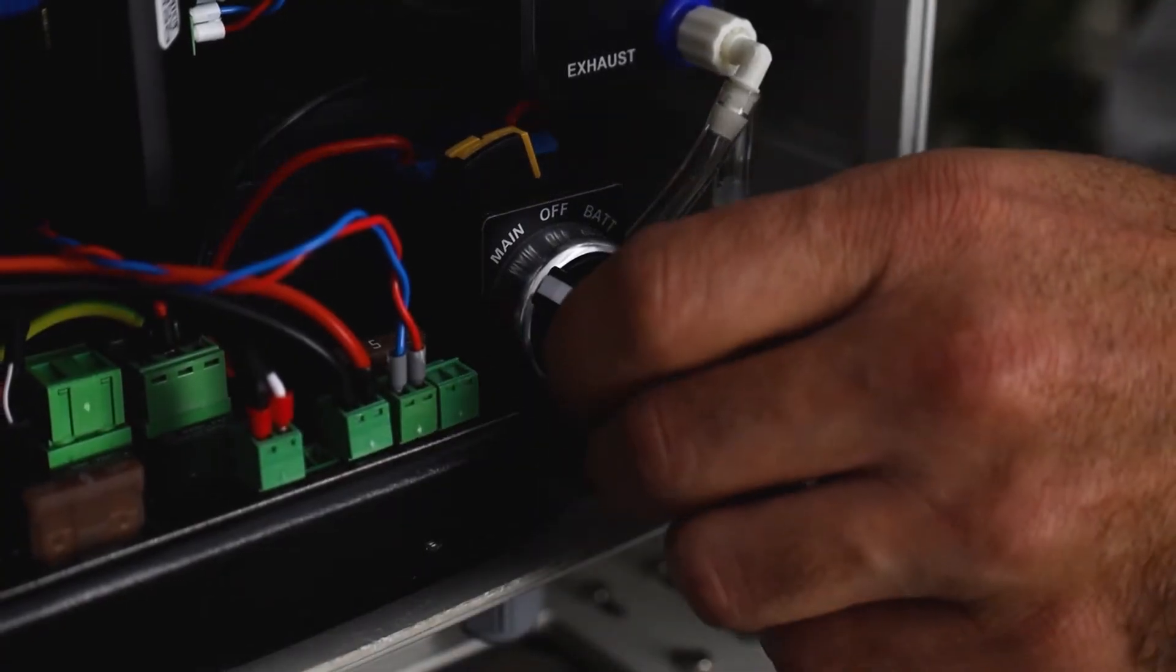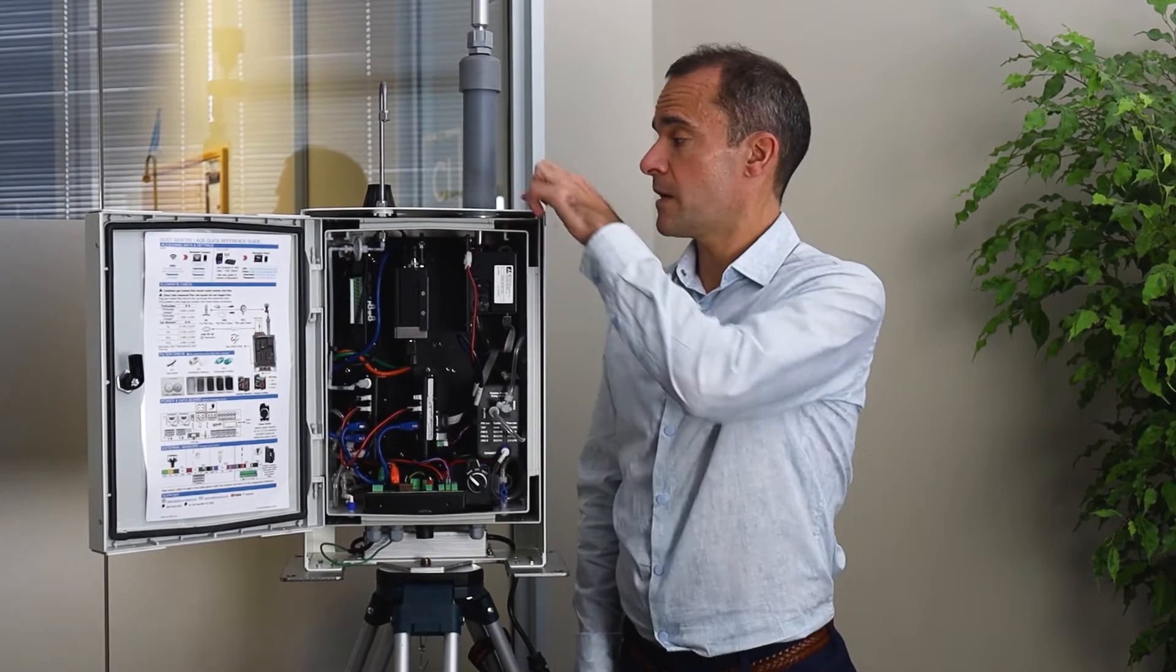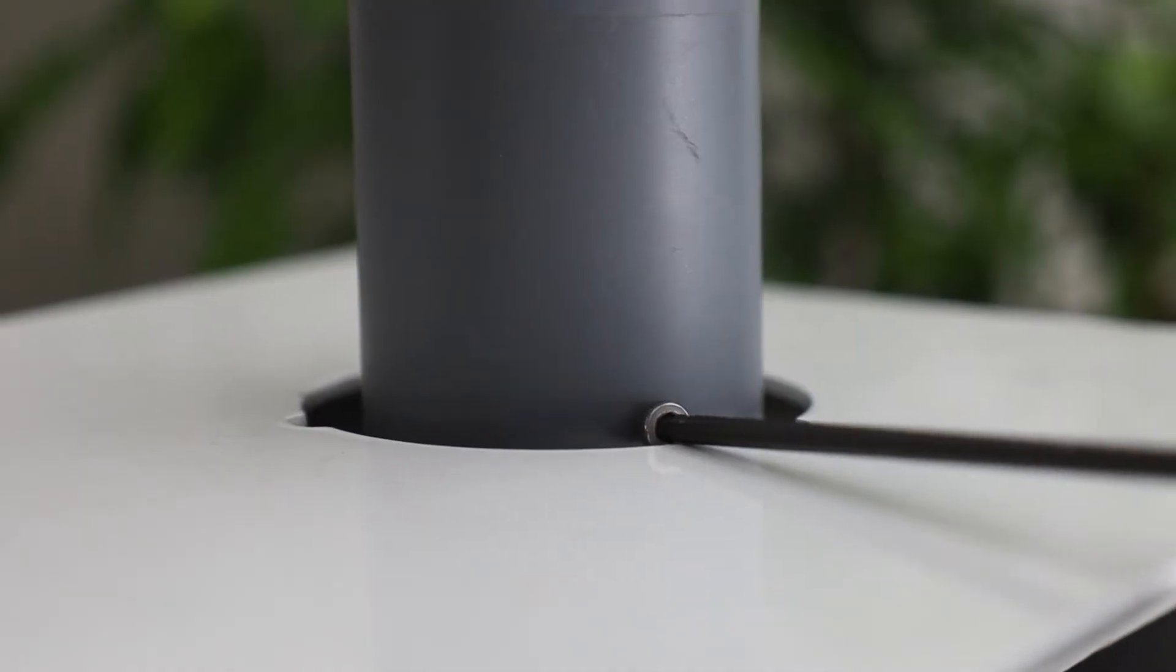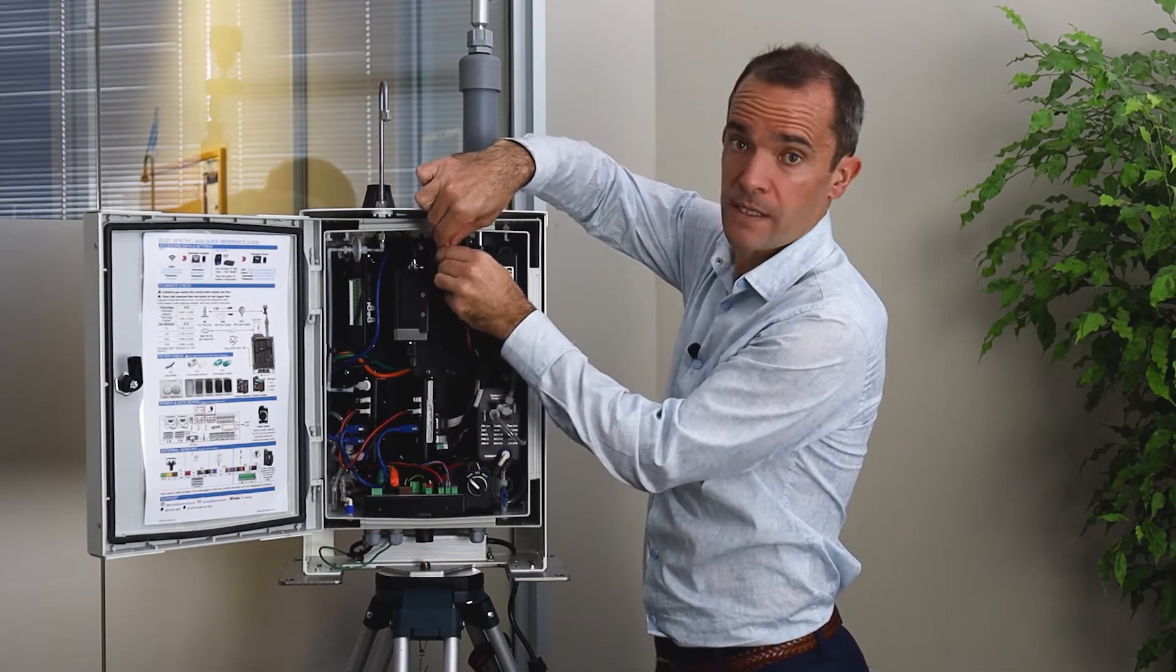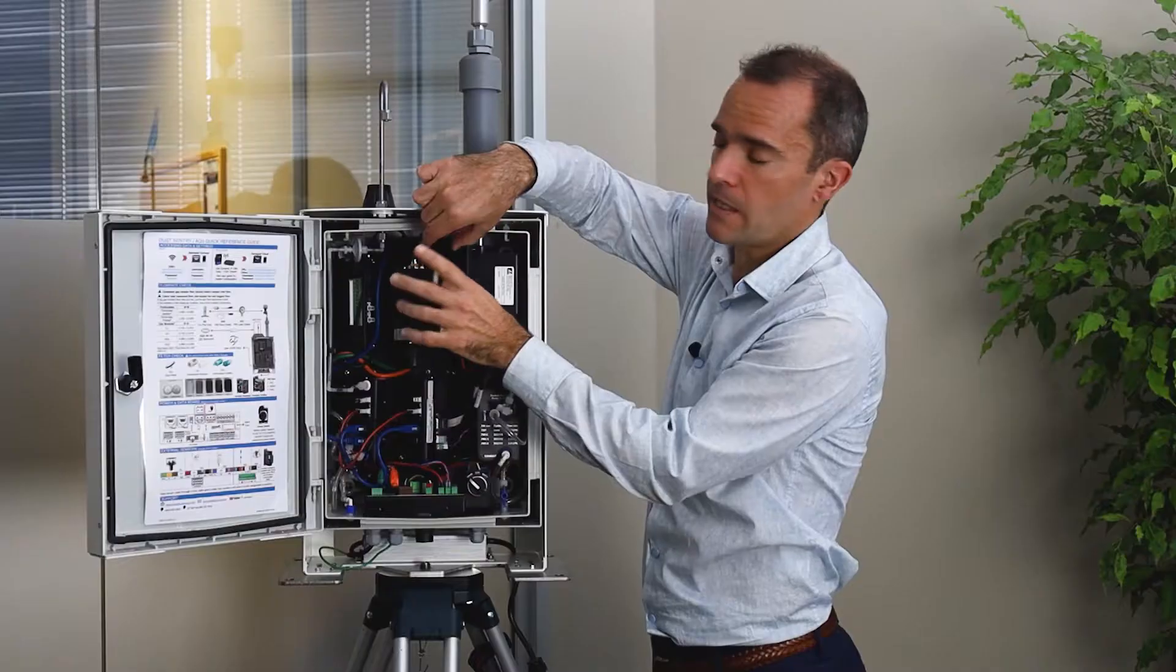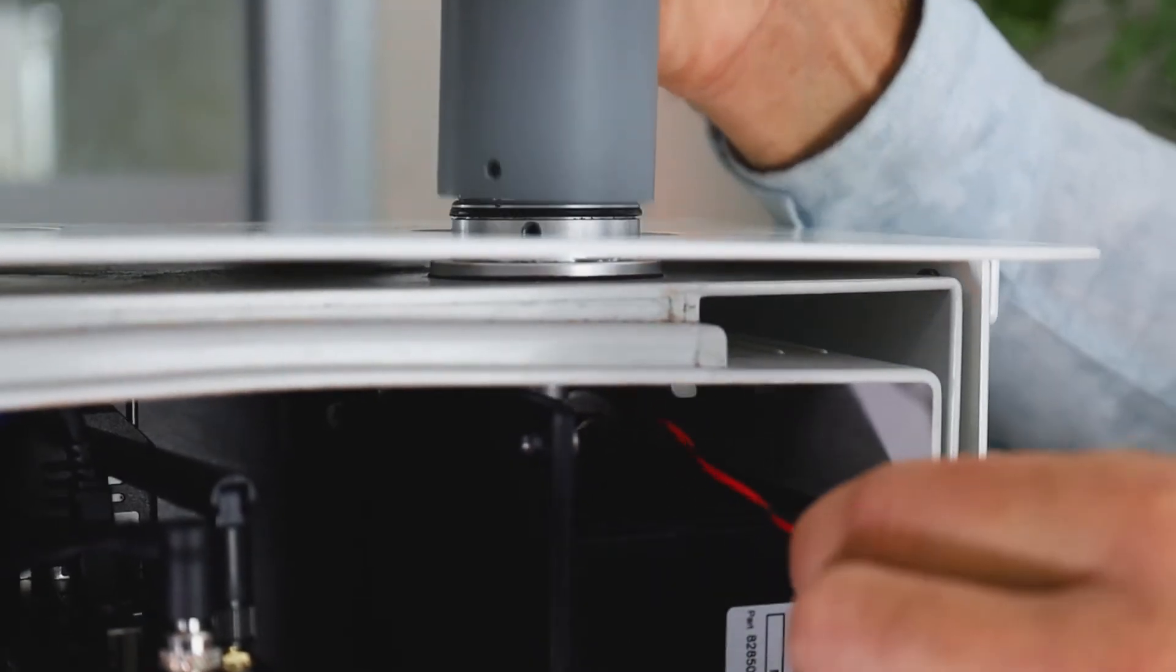We recommend you turn the power off during this replacement. The first step is to undo the three grub screws which are retaining the heated inlet, and then carefully unplug the white plug which is keeping the heated inlet, and then gently remove the inlet.